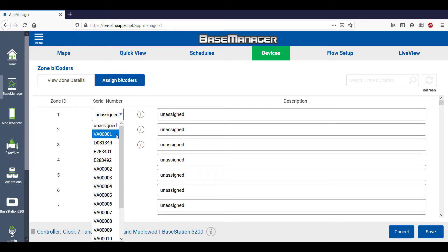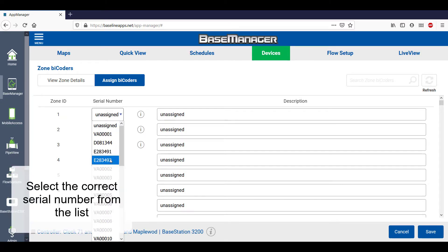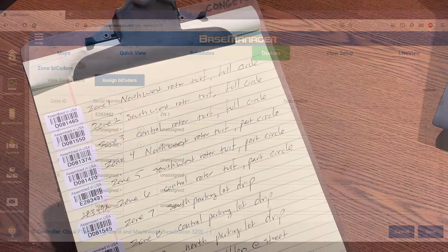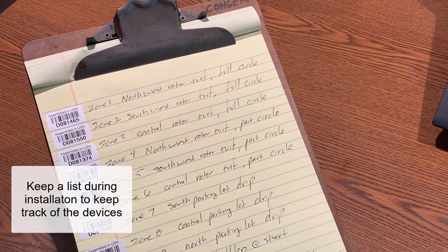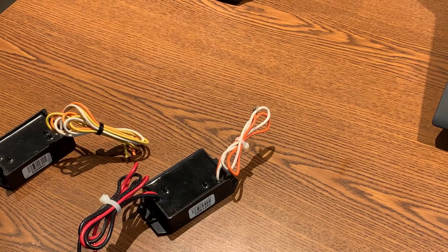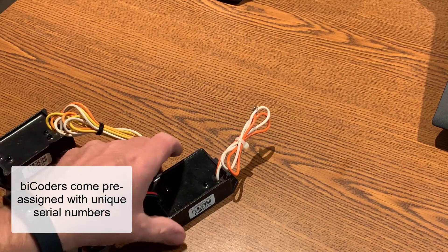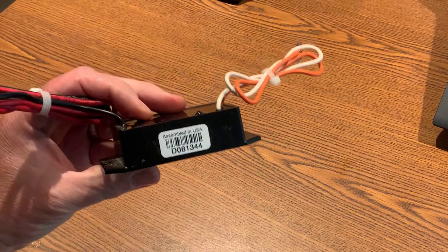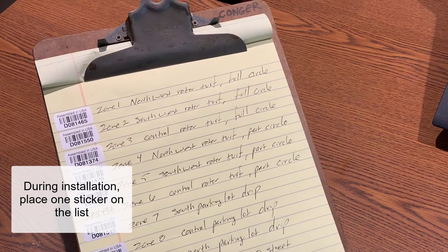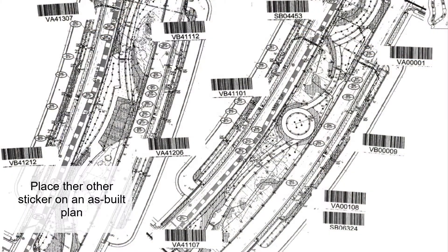I'll look for serial number E283492 and assign that to Zone 1. The reason I selected this particular serial number is based off of the list I created when I installed the bicoders in the field. Bicoders come with a pre-assigned serial number and two extra stickers with that same number. I used one sticker on a list with the description of the location, and I'd suggest using the other sticker on an as-built plan.